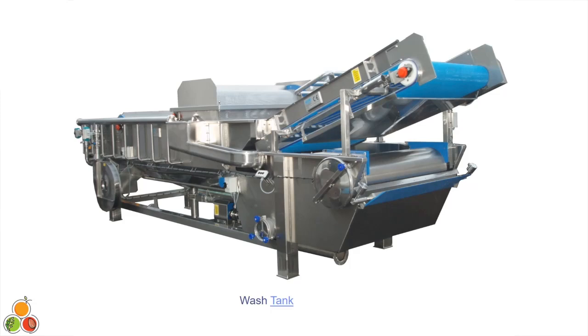So that's different from the old days of plumbing these systems. Oftentimes we had a tank in the unit. We then had your chillers about a quarter mile away in a separate room where all the chemicals were stored. So the time from your pump to your chiller room would be about 2 minutes of transport time. Then you'd inject your chemicals, it'd go through a chiller, it's now cold, it's balanced perfectly. 2 more minutes to get back to your wash system. They typically just enter at the back of the wash system. You may go in hot at 14 parts per million. By the time you get to the end of your wash system, you're down to 10, 9 parts per million.